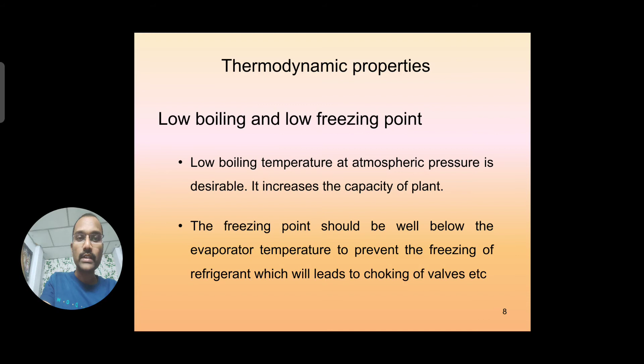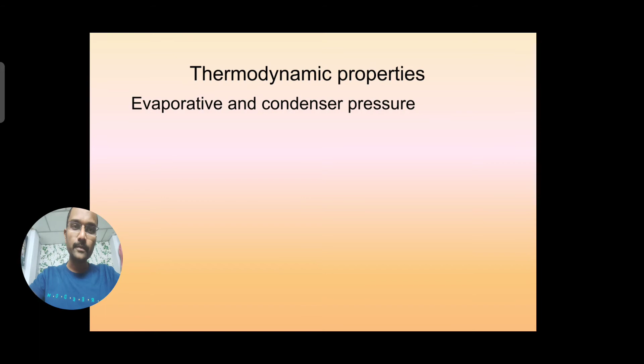Next, moving on to the next thermodynamic property: the evaporator and the condenser pressure. As I already told, it should be positive. You can see this statement, why it should be positive. The refrigerant which is charged into the system is above the atmospheric pressure only, and the pressure which is built up whenever it is under running condition, evaporator pressure and condenser pressure, are different cases, with more pressure in the condenser and lower pressure in the evaporator. But the condition is that the pressures operating at those different places must operate above atmospheric pressure only. If they are operating below atmospheric, that means vacuum conditions, there is a chance of air leakage into the system at any weaker section or at any weaker points.